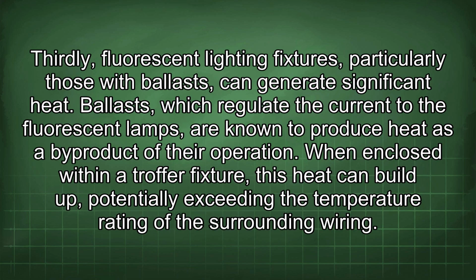Thirdly, fluorescent lighting fixtures, particularly those with ballasts, can generate significant heat. Ballasts, which regulate the current to the fluorescent lamps, are known to produce heat as a byproduct of their operation. When enclosed within a troffer fixture, this heat can build up, potentially exceeding the temperature rating of the surrounding wiring.